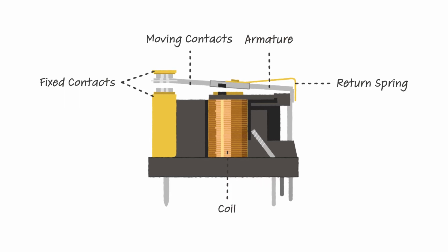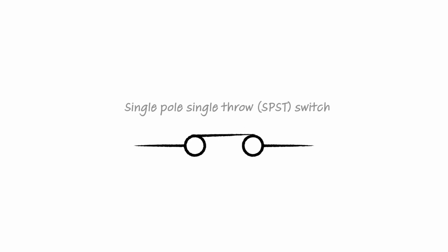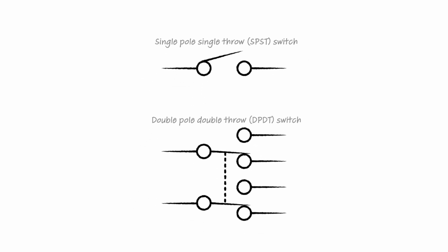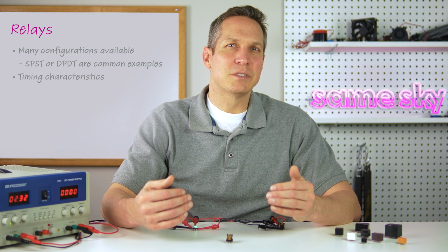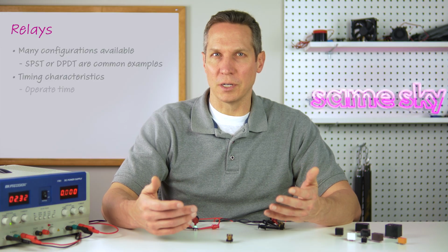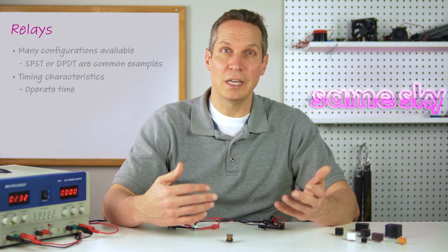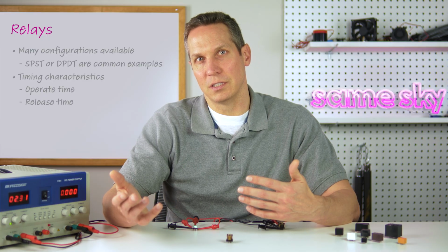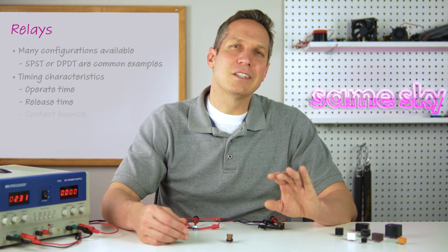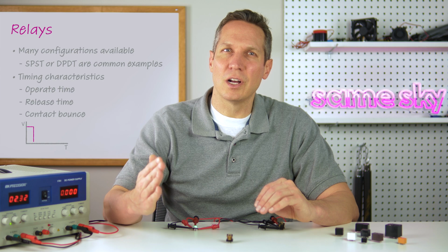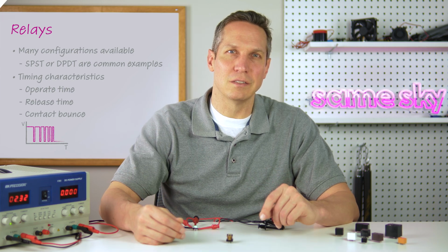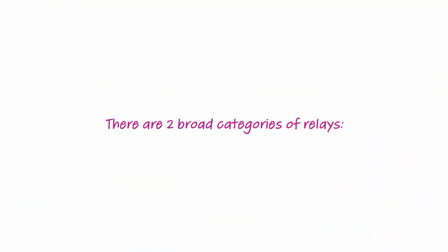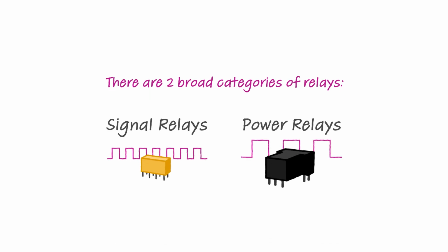Relays come in many different configurations, such as single pole, single throw, or double pole, double throw. They also have several timing characteristics like operate time, which is how long it takes for them to engage, release time, how long it takes for them to disengage, and contact bounce, which is how much the contact will bounce between the two states. With that brief introduction, let's separate the two broad categories of relays you'll likely see.